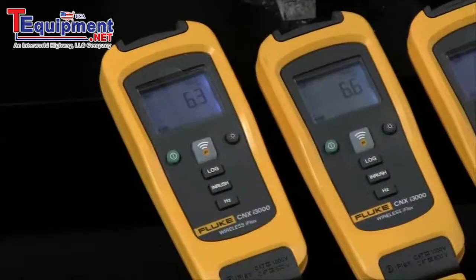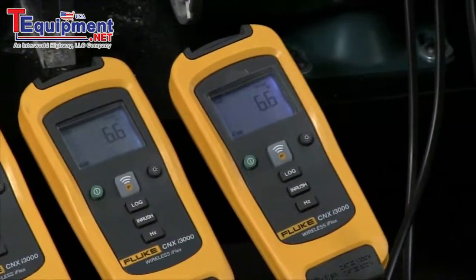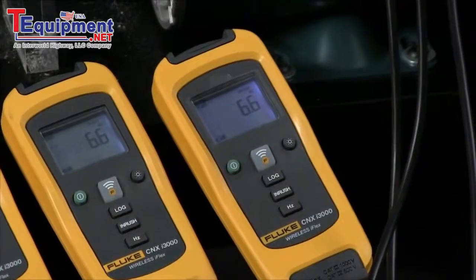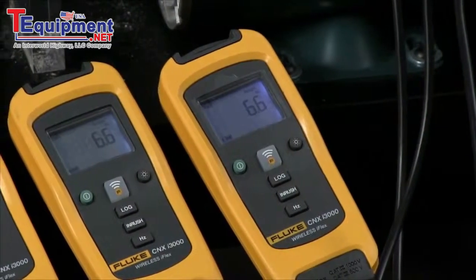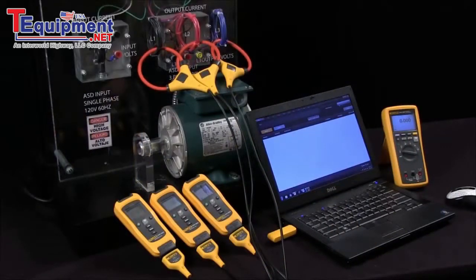One would be to read directly off the screens you see on each of the i3000 iFlex modules. We were reading the current reading on there: 6.4 amps, 6.6, and 6.6. These are on the respective phases L1, L2, and L3.